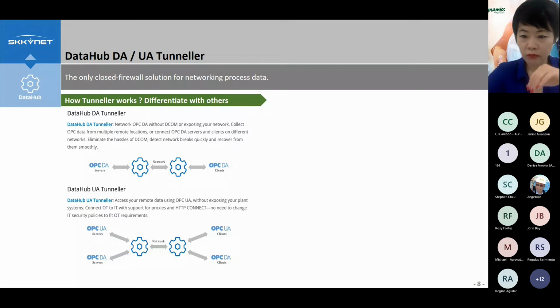In order for you to communicate directly over a network, DataHub eliminates the hassle of using DCOM, and you can collect OPC data from multiple network locations without exposing your network. The DataHub UA tunneler is the same as the DA tunneler, except you use OPC UA instead of OPC DA, depending on what the third-party application requires. So it's based on user preference whether you use DataHub DA or DataHub UA tunneler.